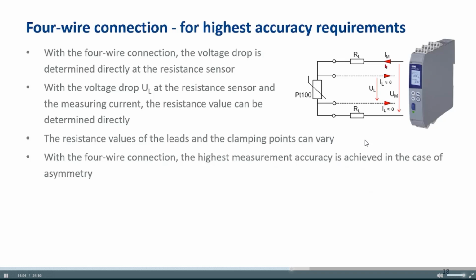And especially it helps if your system is asymmetrical. This means maybe you have a slightly different resistance here than there, because the terminal resistances are a little bit different. Then, if you have such a situation, it doesn't matter for the 4-wire connection, it will compensate this. And if it is not symmetrical, you would have a little error with a 3-wire connection. 4-wire connection is not very often used in process technology. This is used if you work with a reference instrument, if we want to have it as good as possible, or in labs sometimes they work in 4-wire technology, not so often in process technology.